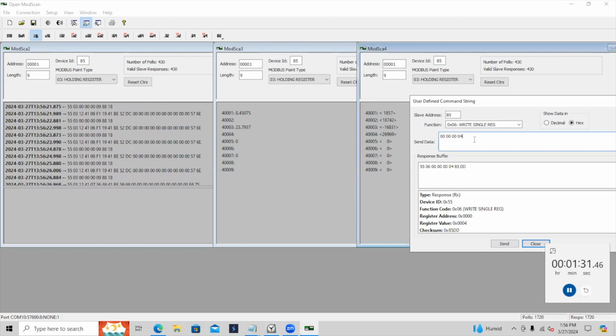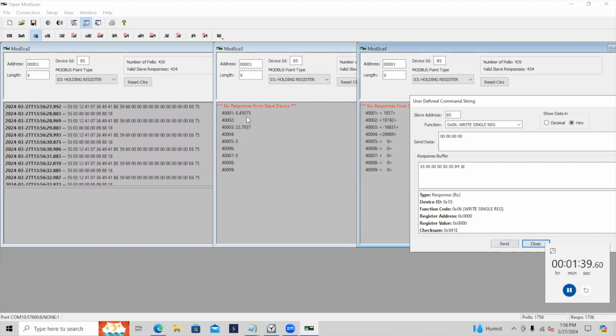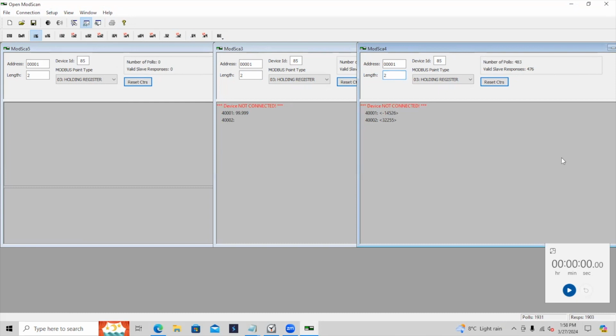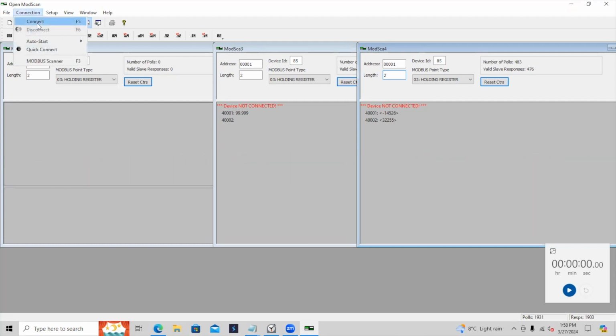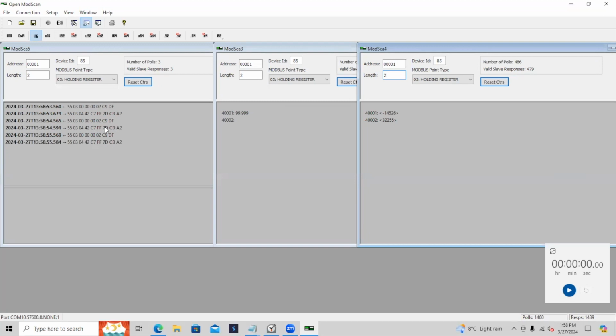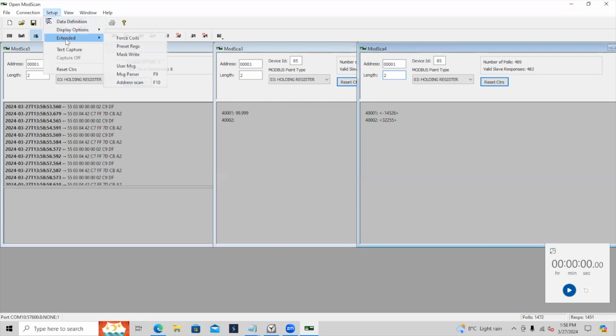We can now stop the measurement again by sending the 00 command. And the sensor is now stopped, and the 99.99 will be returned. So now we've shown that we can do a bulk data dump. Now we're going to show that we can just recall the pH number. So we'll turn the sensor on, and then connect to the COM port, COM10, checking the baud rate. Okay. We can see the sensor is responding.